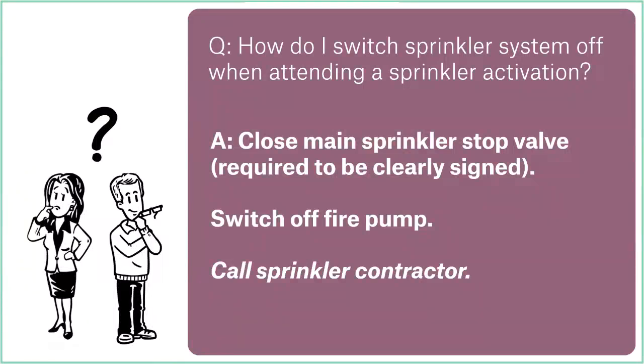Let's say that the pipe's been damaged and there's water coming out. You want to turn it off. You turn it off at the main stop valve, simple as that. The fire pump, if there is one present, will be running against what's now called a closed head. Okay, so because you've closed that stop valve, and that main stop valve, by the way, is going to be at the installation control valve, then the fire pump won't like that long term. The fire pump is there to run to destruction. So once you've closed the stop valve, that fire pump is going to keep going for a while. Okay, so it's not going to blow up immediately, but it won't like that long term.